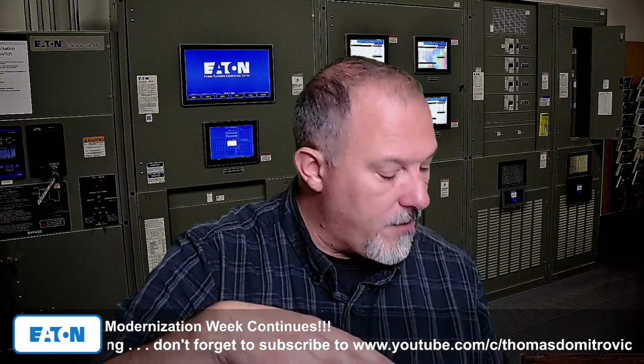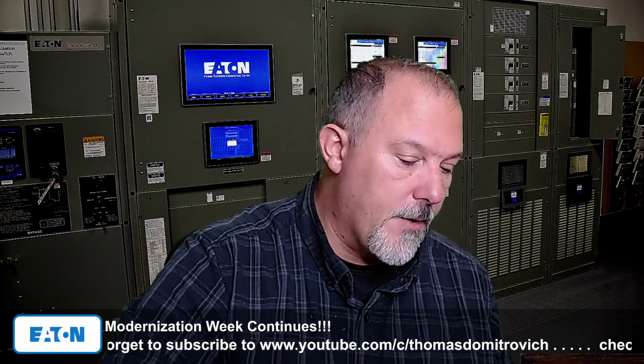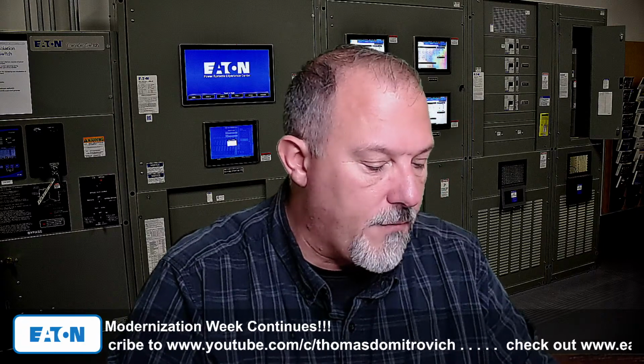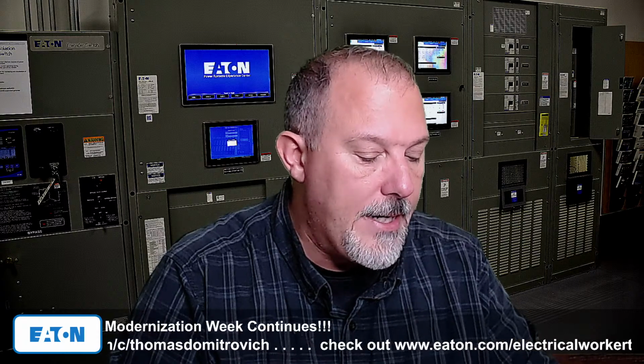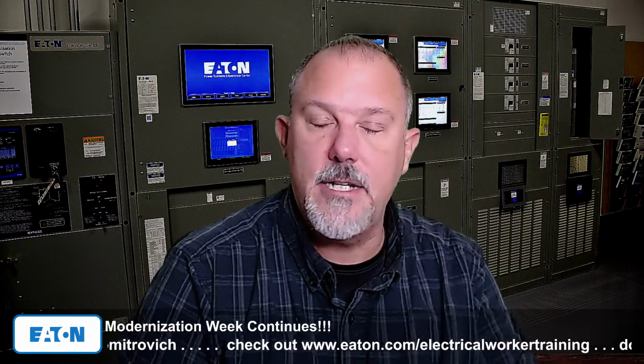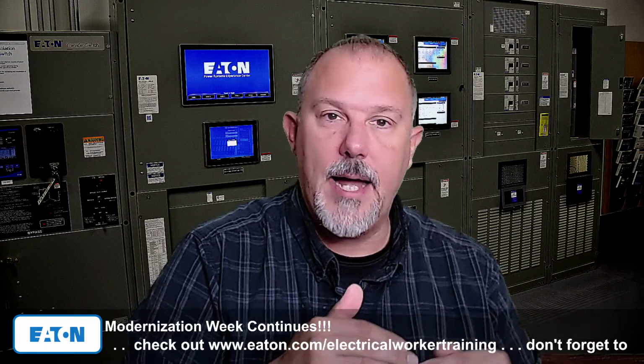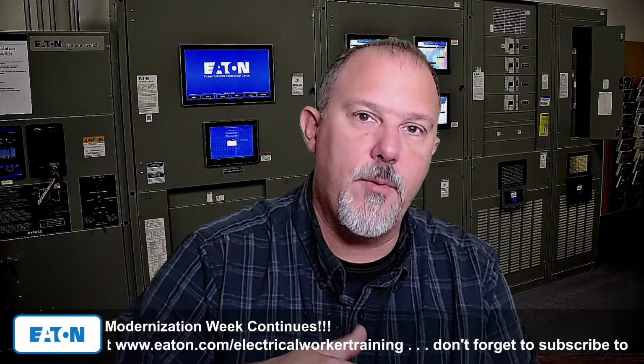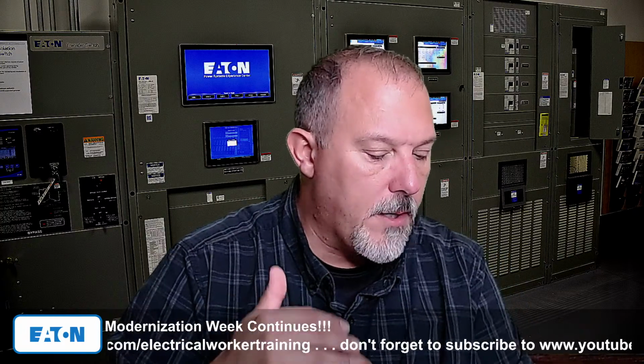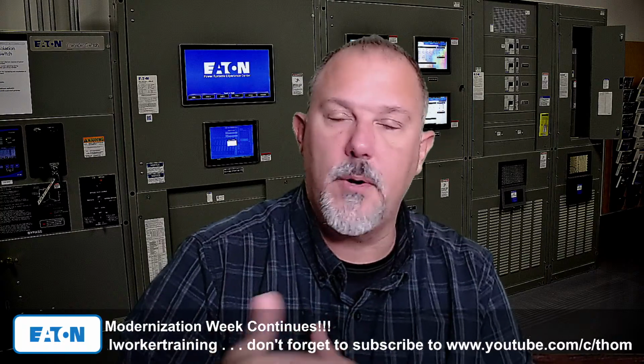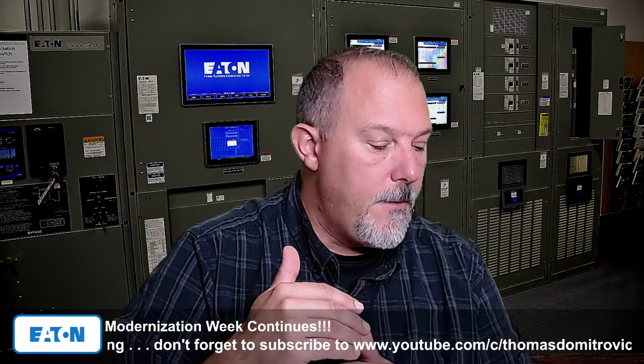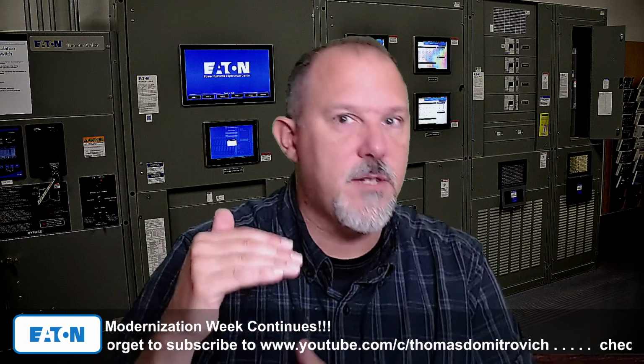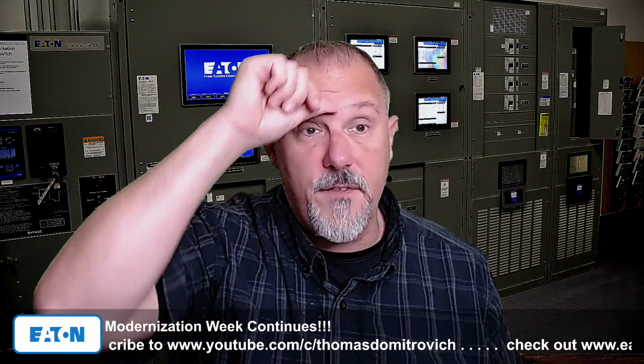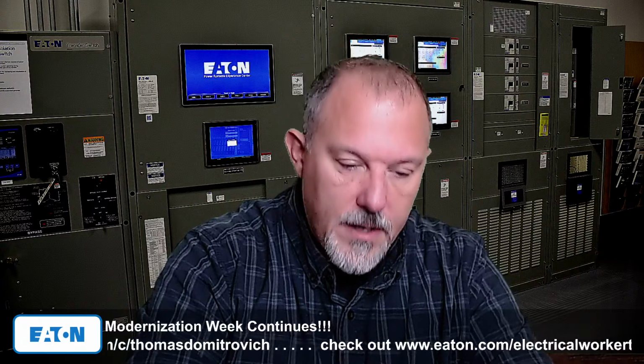Now, when you get into the floor outlets, there is floor receptacles. Receptacle outlets in or on floors shall not be counted as part of the required number of receptacle outlets unless located within 18 inches of the wall. So I could be in the floor, but I have to be within 18 inches of the wall to be permitted to be counted as part of the number of receptacle outlets. So I would say there's no minimum. A maximum is 5.5 feet, as in 210.52. Hopefully that helps you.